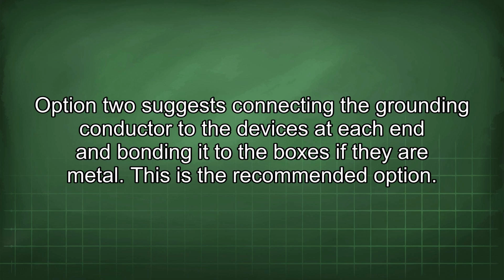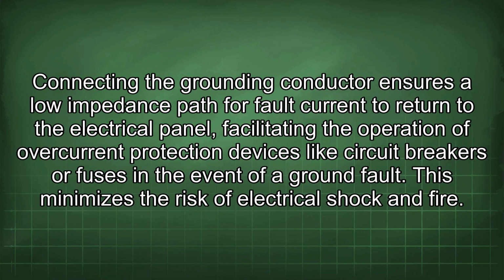Option 2 suggests connecting the grounding conductor to the devices at each end and bonding it to the boxes if they are metal. This is the recommended option. Connecting the grounding conductor ensures a low impedance path for fault current to return to the electrical panel, facilitating the operation of overcurrent protection devices like circuit breakers or fuses in the event of a ground fault. This minimizes the risk of electrical shock and fire.